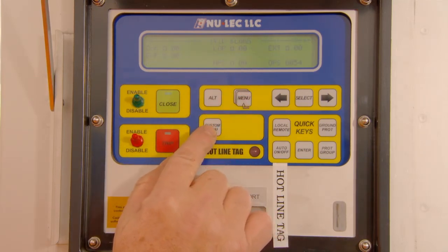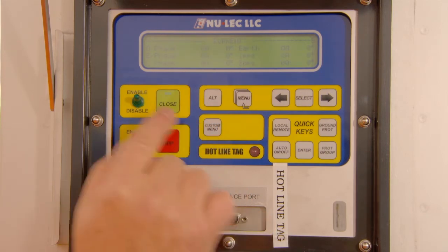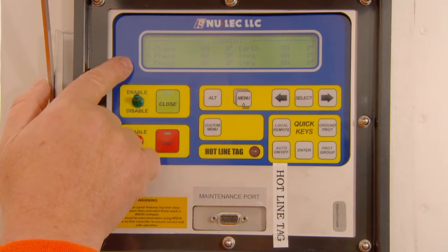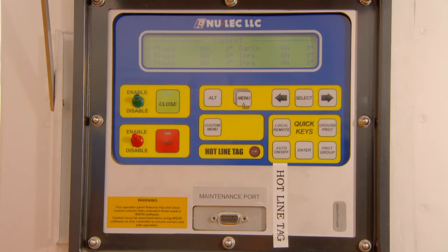If you press the Custom Menu again, the Current screen appears. You can see any current flow that is actually going through the unit. If you're putting this recloser in or out of service, you would want to be viewing this display. If your leads are removed and the recloser is open, there will be no current flow. When you install your leads onto the actual unit with the bypass switch closed and the recloser open, you will still see zero current flow.